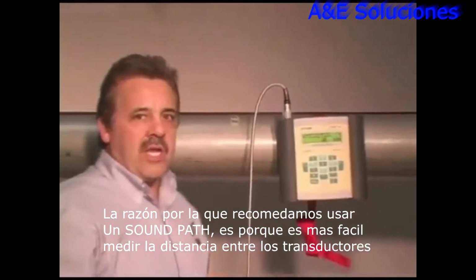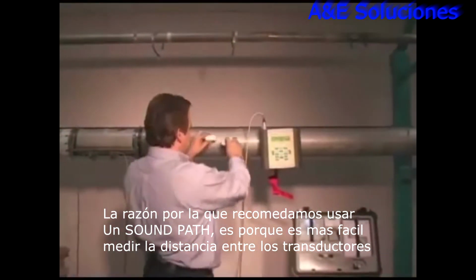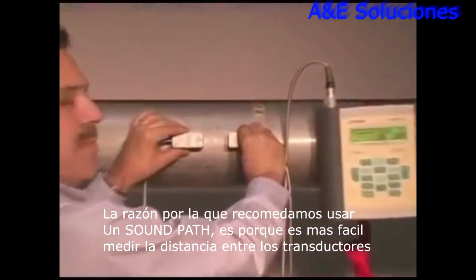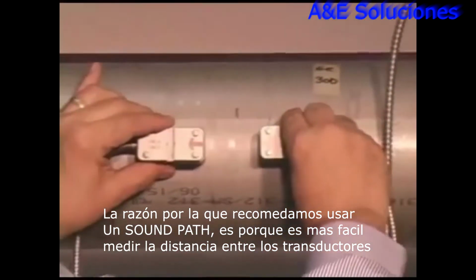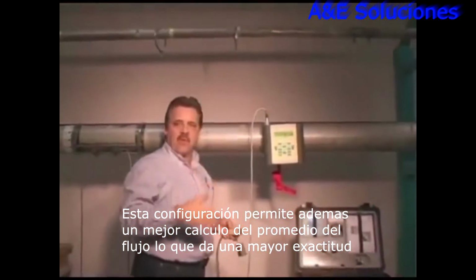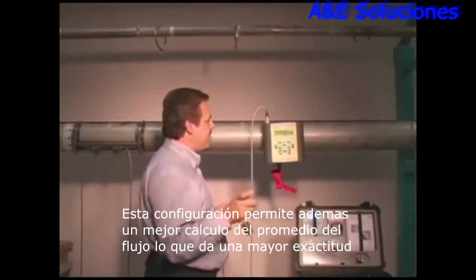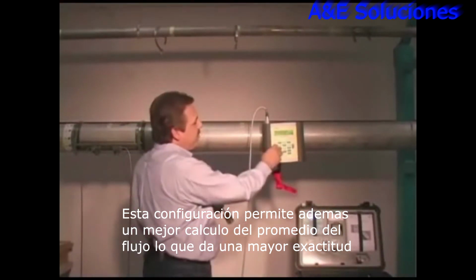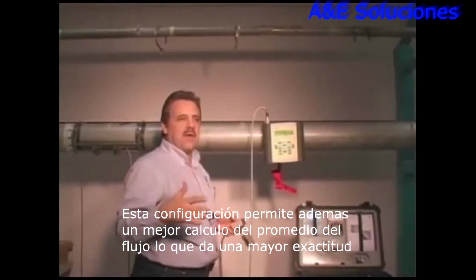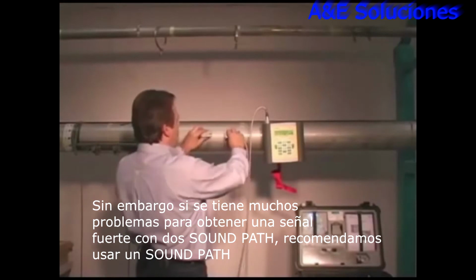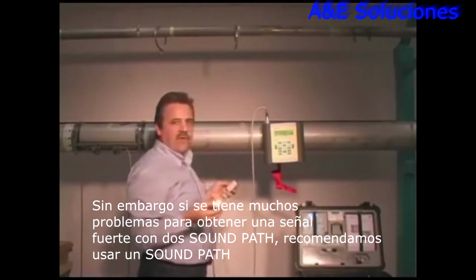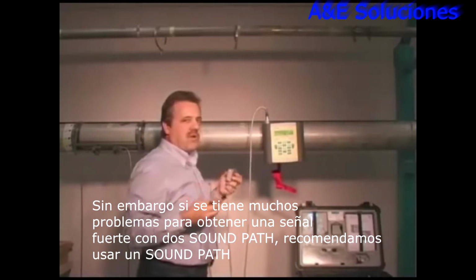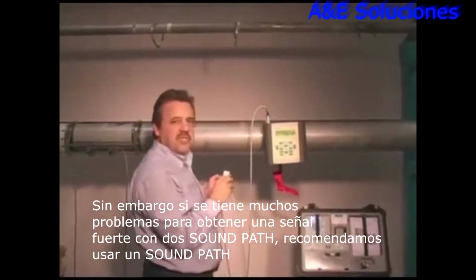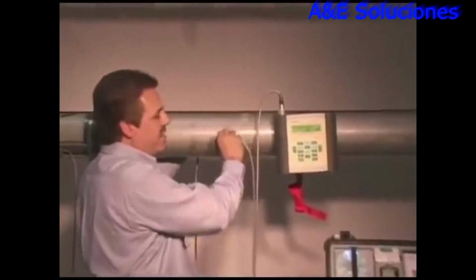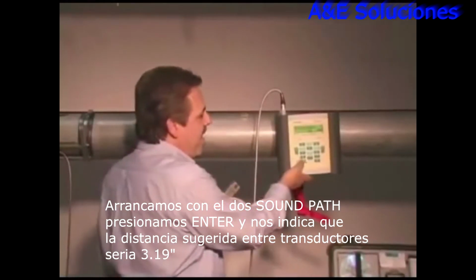Now we recommend starting at 2 sound paths. It makes mounting the transducers and spacing and measuring the spacing distance much easier. And B, going through the liquid twice provides better averaging of the flow profile, so you can get potentially better accuracy than 1 sound path. The only time we traditionally would recommend 1 sound path is when you install it with 2 sound paths, and now you're struggling to get a strong signal. Then you change it to 1 sound path, and you would change the configuration. So we're going to start it off 2 sound paths.